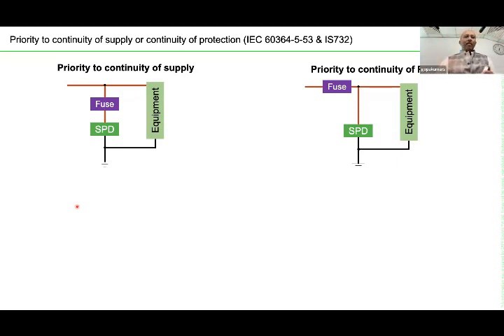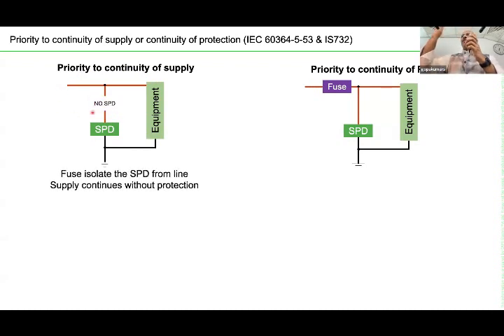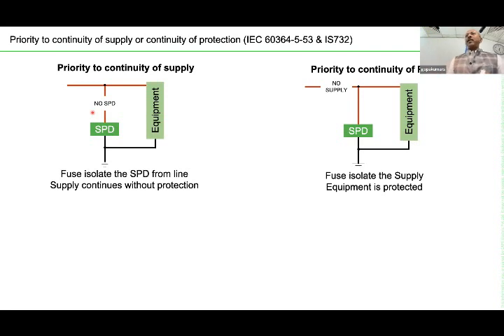Now, you can see here the backup protection is made in, for example, this is the parallel circuit. There is a fuse, for example, and in this case, the fuse is in the line. The first one on the left side, in this case, you are giving priority to continuity of supply. Because once the SPD fails, the HRC fuse isolates the SPD from the circuit, and your supply is continuous: priority to continuity of supply. The second one, once the SPD fails, the supply is isolated. So this is called priority to continuity of protection.